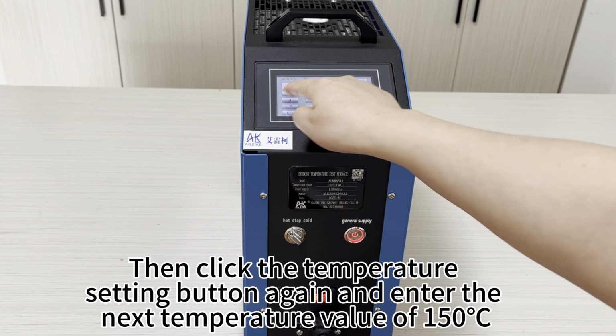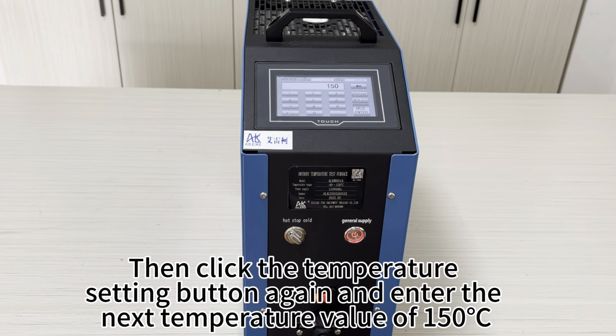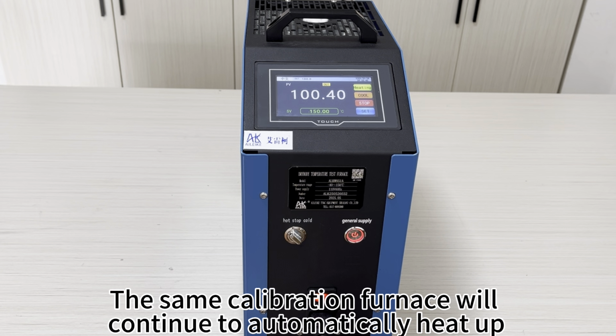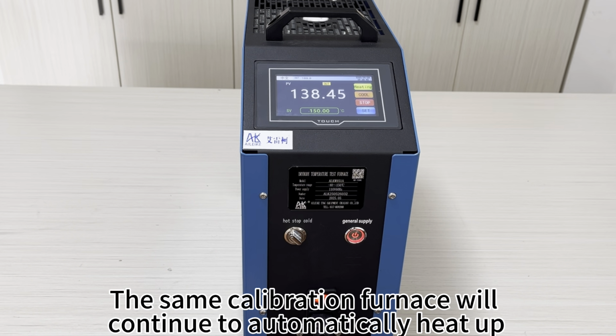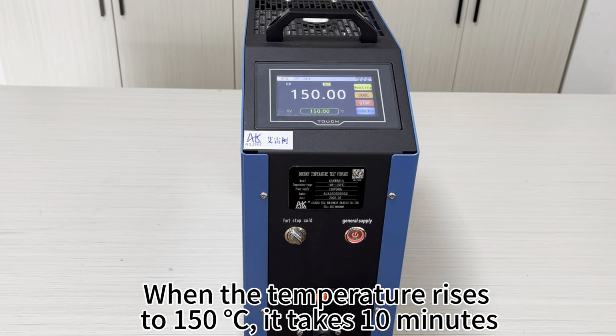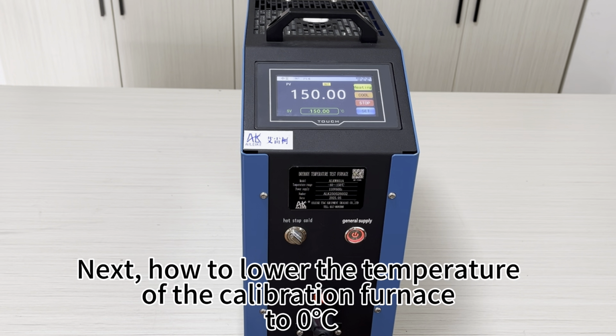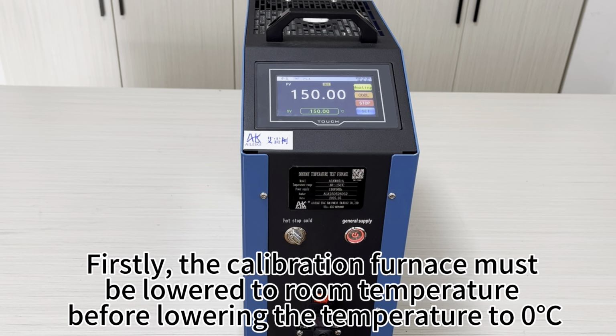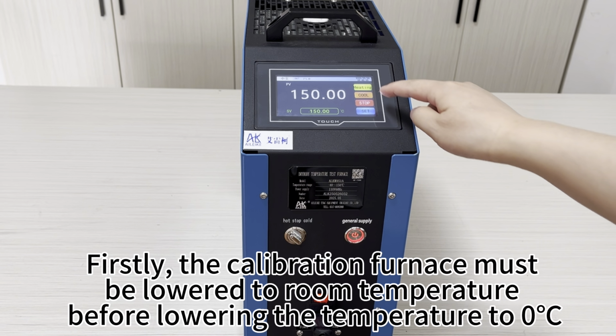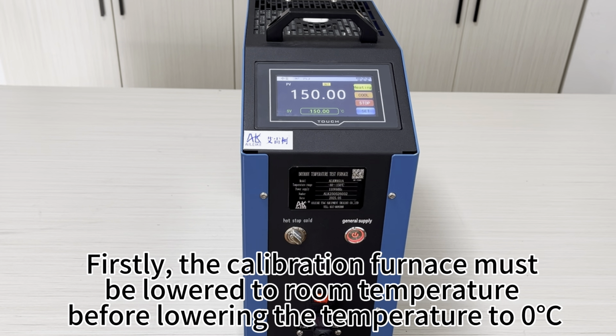Then click the temperature setting button again and enter the next temperature value of 150 degrees Celsius. The same calibration furnace will continue to automatically heat up. When the temperature rises to 150 degrees Celsius, it takes 10 minutes. Next, how to lower the temperature of the calibration furnace to 0 degrees Celsius. Firstly, the calibration furnace must be lowered to room temperature before lowering the temperature to 0 degrees Celsius.